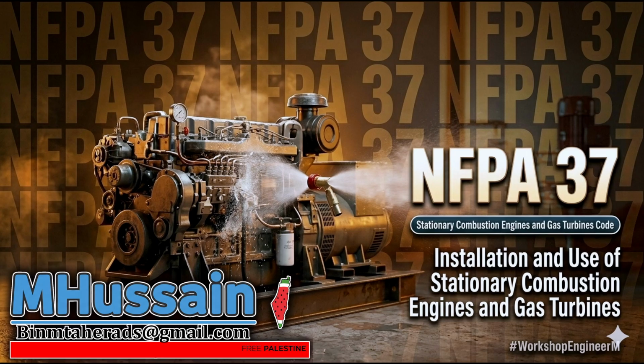Wait, suitable? That's a terrifying amount of leverage for an inspector. It really is. By that wording, you could put a 5,000-gallon tank on the third floor of an office building, as long as you convince the AHJ it's suitable. But what one fire marshal thinks is suitable might be totally different from another. Exactly. One might just want standard sprinklers and a concrete curb. Yeah. Another might demand a fully flooded chemical clean agent system and a foam purge system. So how do engineers handle that ambiguity? By never designing in a vacuum. If you're going to use that exception, you have to bring the fire marshal into the conceptual design phase.